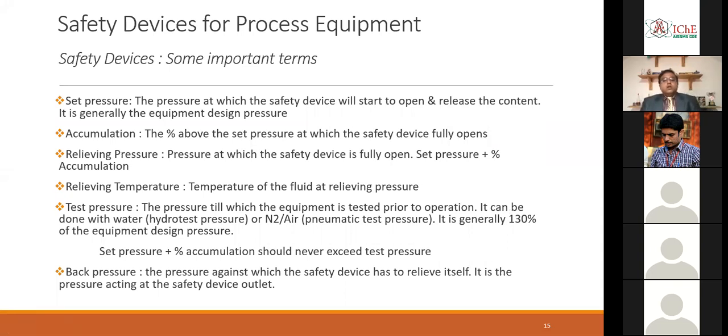So this is a very interesting aspect. It can cross the design pressure, but it should never cross the hydrotest or the test pressure. So when we give relieving pressure, we have to make sure that my set pressure plus percentage accumulation has not exceeded the hydrotest pressure of the equipment.